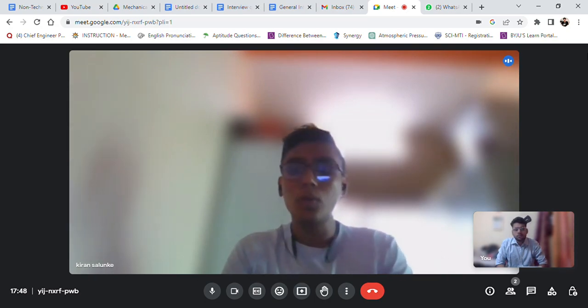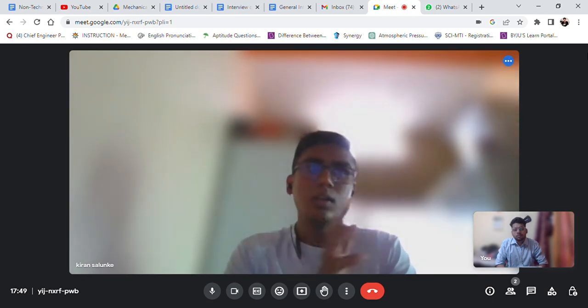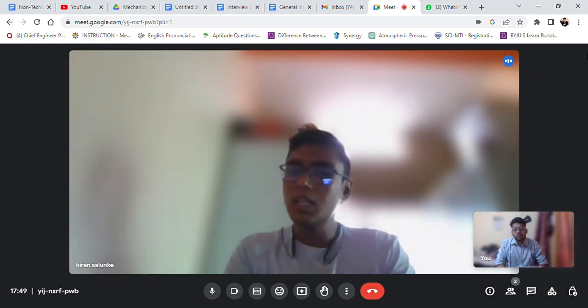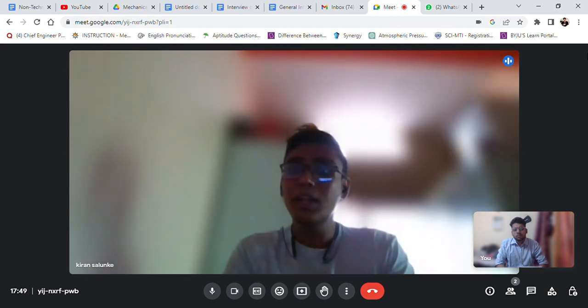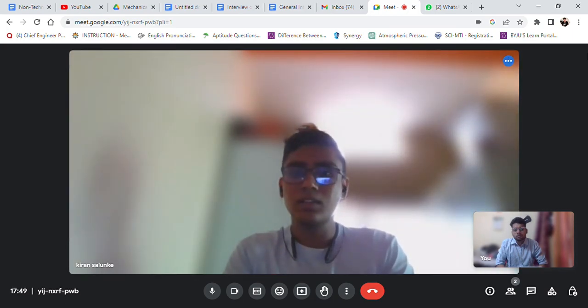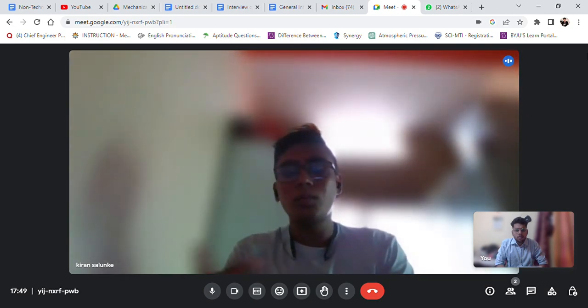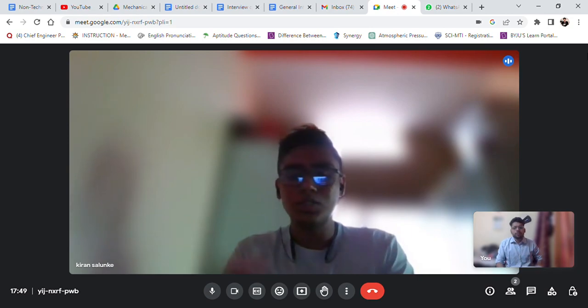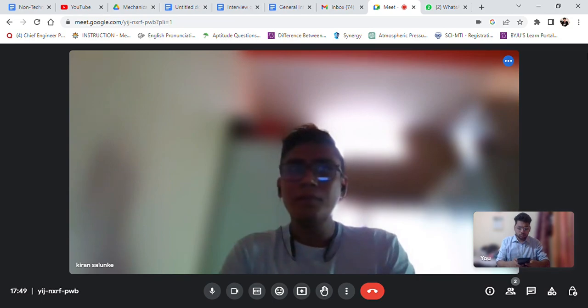Also, sir, if some amount of liquid goes inside the compressor, we know that liquids are incompressible in nature, so it damages the compressor very harshly. Okay. And suppose a banging and rattling sound is coming from the compressor, we know that moisture has been introduced to our system. We have to remove that moisture. How do you remove that moisture? Sir, the moisture is removed by fitting a dryer just after the condenser. That means it has silica gel.